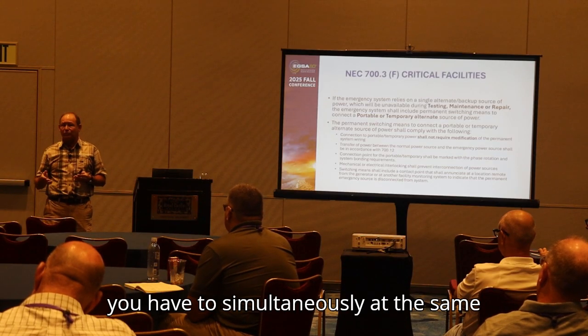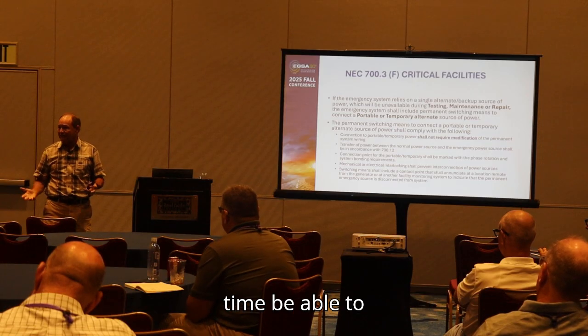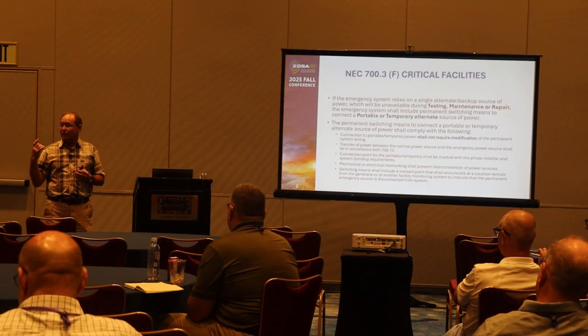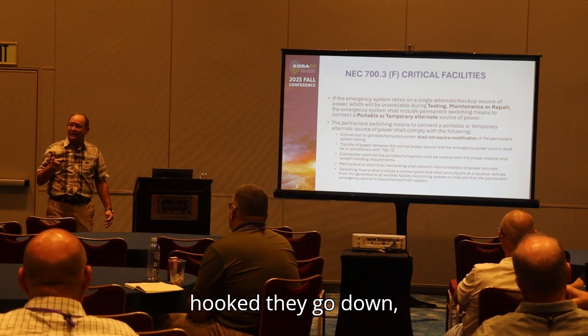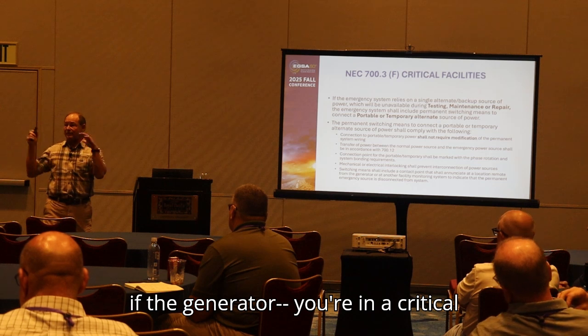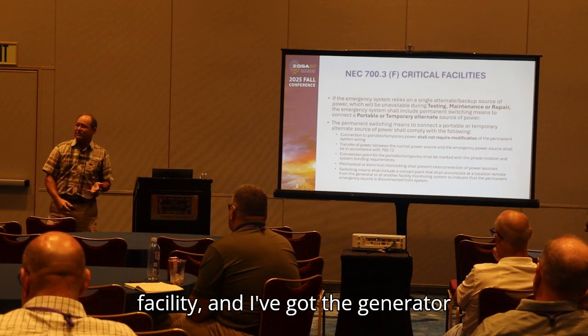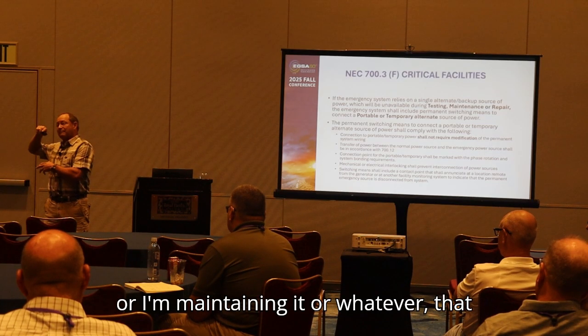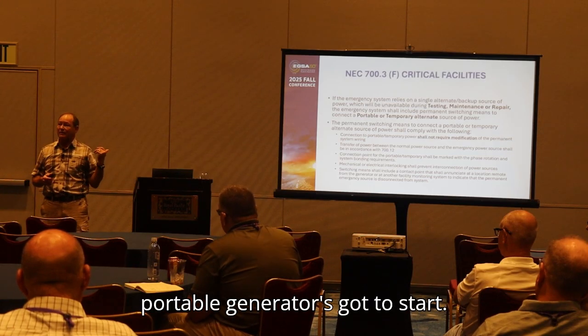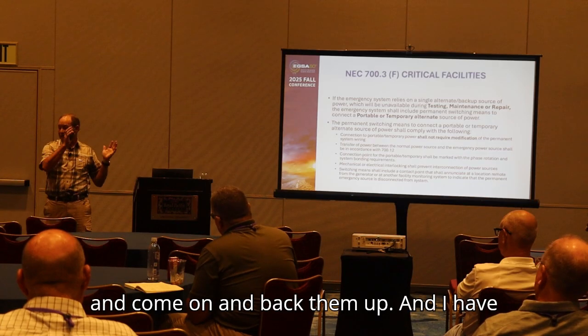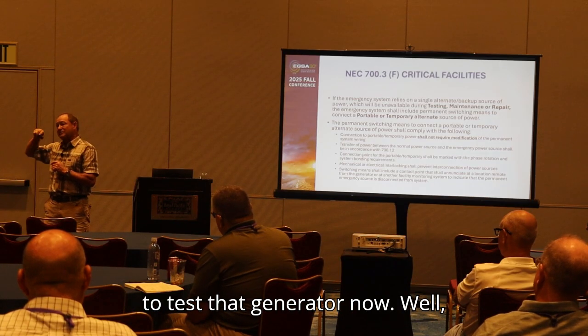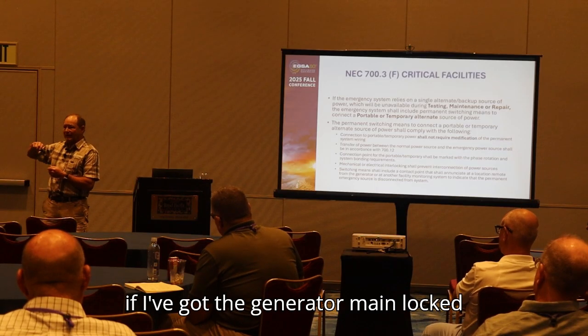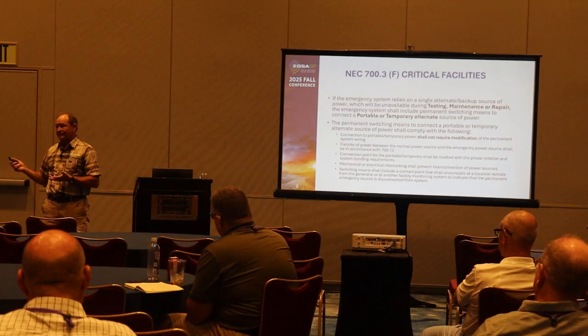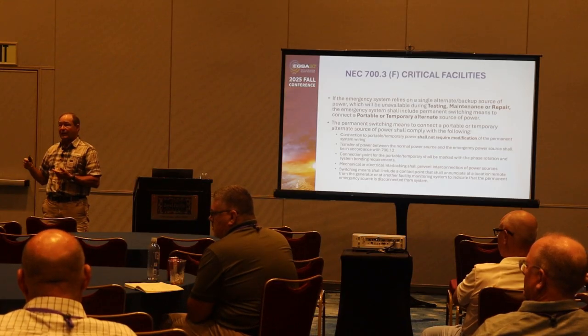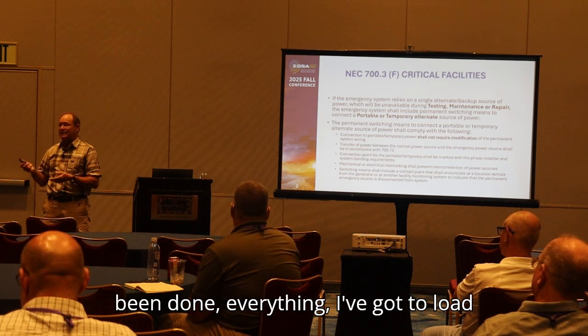If it's deemed critical, you have to be able to simultaneously load bank and have a portable generator hooked up. If they go down, if the generator, you're in a critical facility, and I've got the generator radiator pulled off, or I'm maintaining or whatever, that portable generator's got to start and come on and back them up. And I have to test that generator now. Well, I can't, if I've got the generator main locked out, there's no way to test it once you get the radiator back together. Is that what you're saying? Yeah, once it's up and running, the oil's been done, everything, I've got to load test the generator.